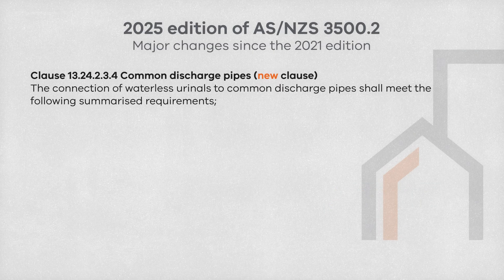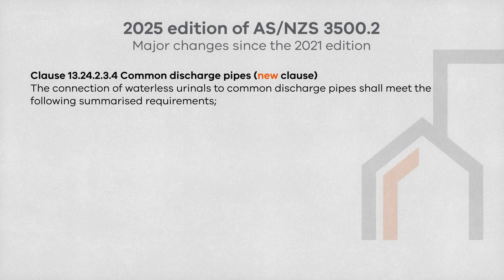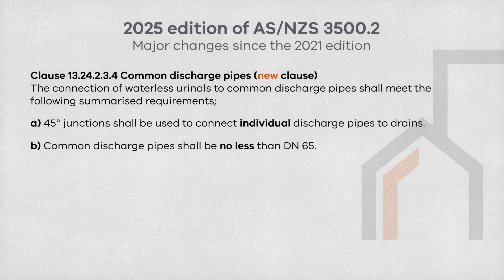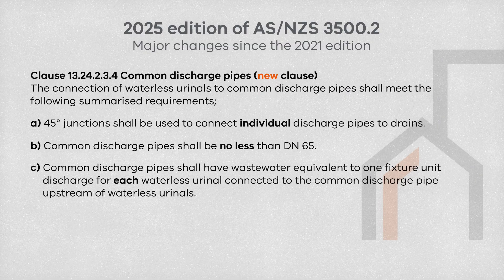A new clause has been added to the standard outlining the connection requirements that waterless urinals must comply with when connecting to common discharge pipes. There are five new requirements. First, 45-degree junctions shall be used to connect individual discharge pipes to drains. Second, common discharge pipes shall be no less than 65mm. Third, common discharge pipes shall have wastewater equivalent to one fixture unit discharge for each waterless urinal connected upstream.